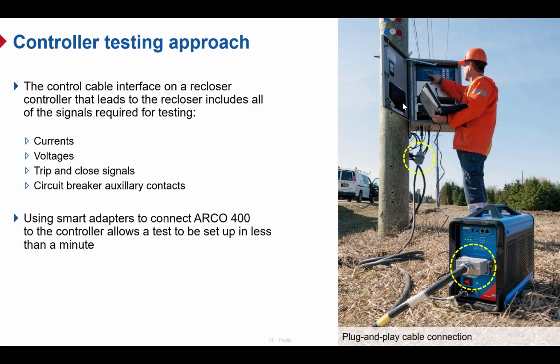Now let us look at the controller testing approach. The key idea here is that all signals we need for testing are available through the controller cable interface. This includes current and voltage measurement, as well as trip and close commands and the circuit breaker status signals. So instead of testing multiple parts separately, we can access everything from one point, the controller interface.